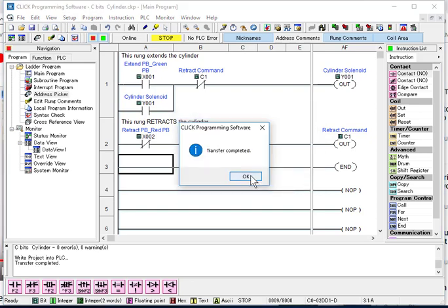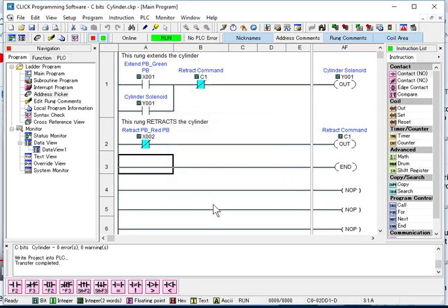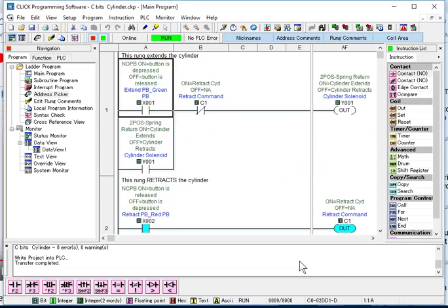Changing it, taking out a rung. So now, you see we're not able to start the system because if we look, Y1 is blocked by C1 being off. The problem is, it looks like we're telling it to retract.